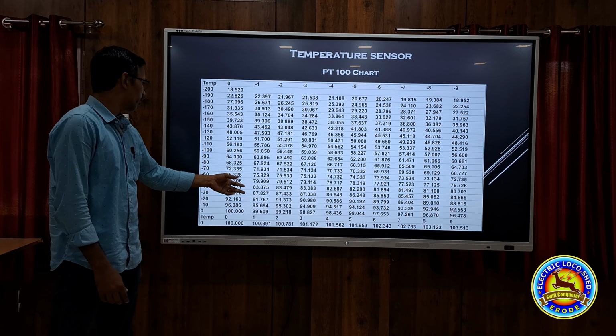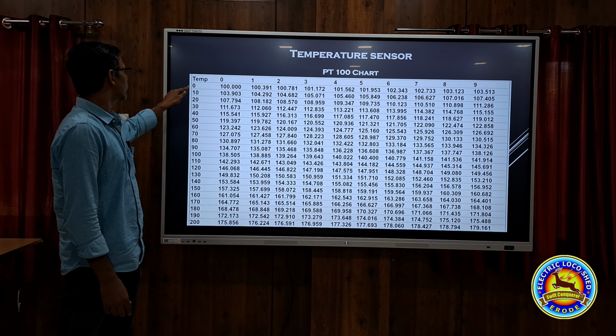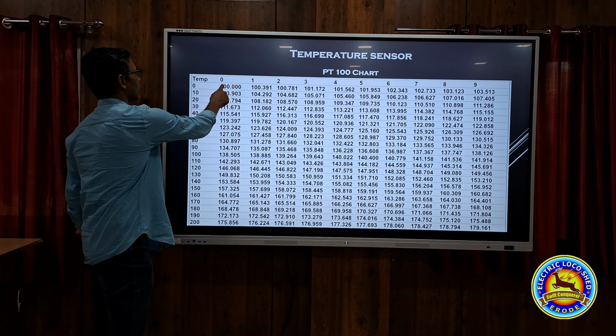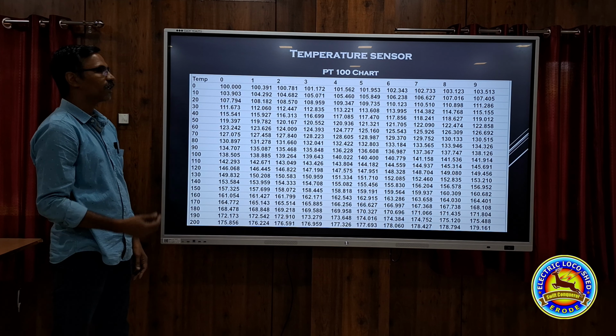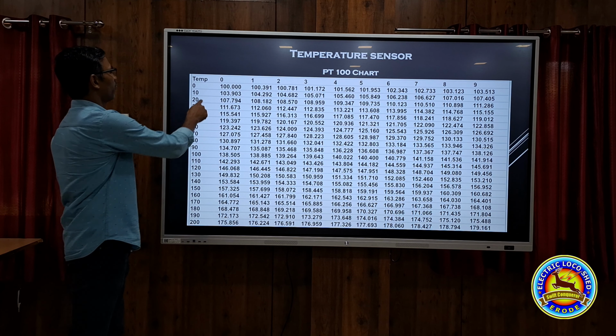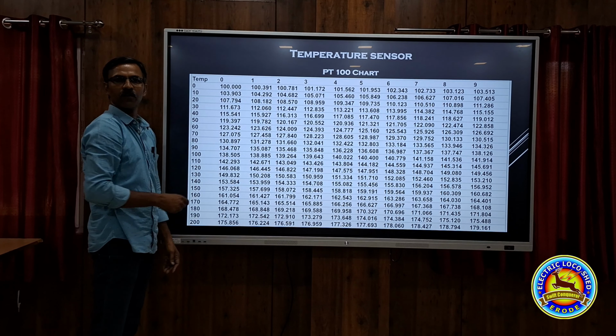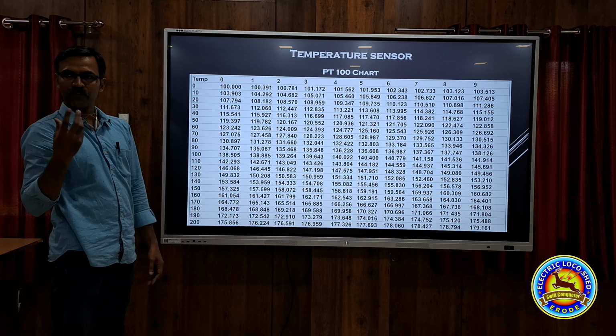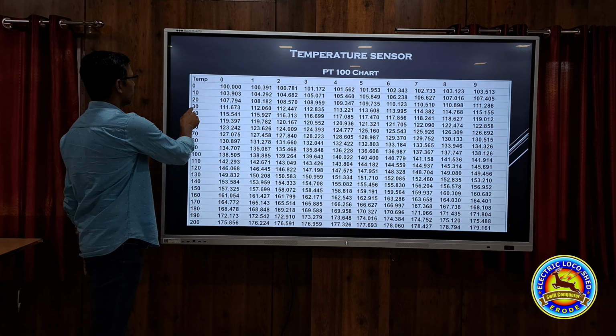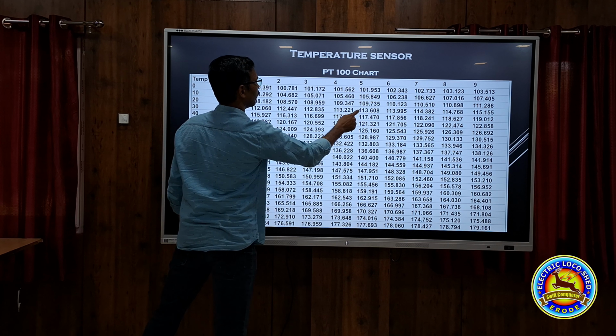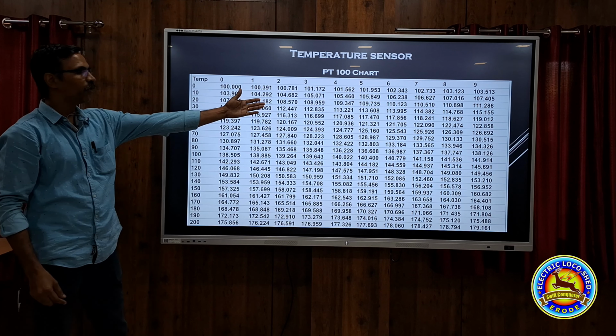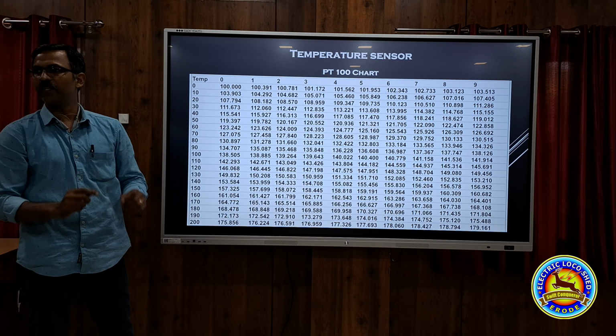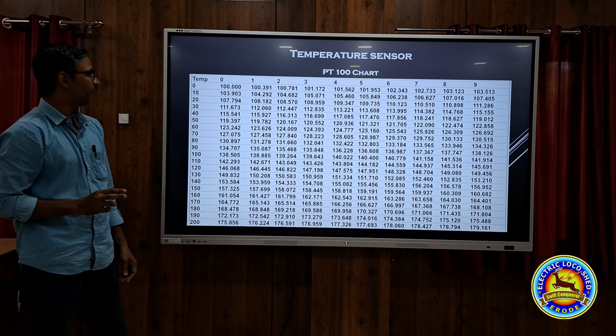This is the zero temperature. I will go to the next page. See, this is the 0 and this is also 0, so this is the 0th position. If you want to know the resistance at 1 degree Celsius, you look at 0, 1. If you want the resistance at 35 degrees Celsius, you look at 30, then 5. So it will be 113.608 ohms across that element. In the two elements, you can get these values. The values should be equal, or the difference can go up to a maximum of 0.4 ohms.